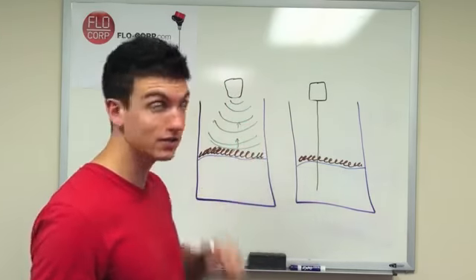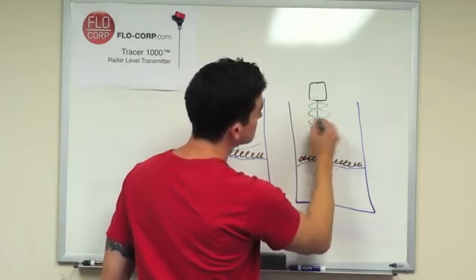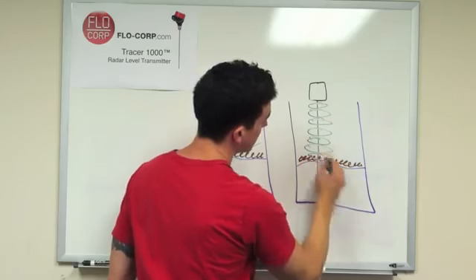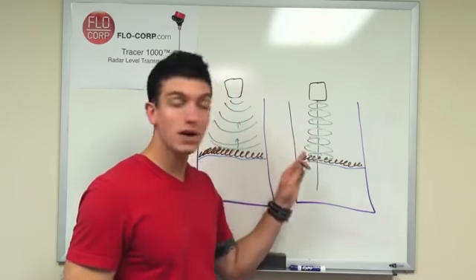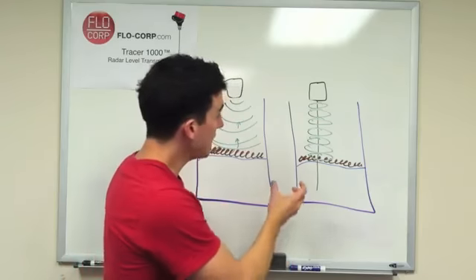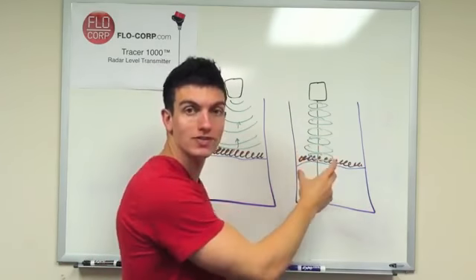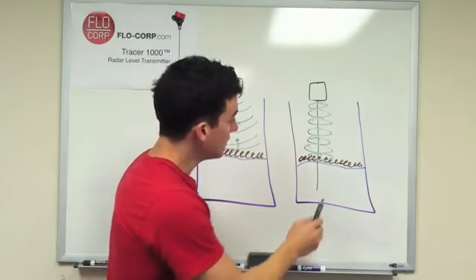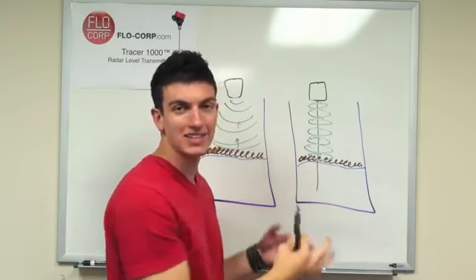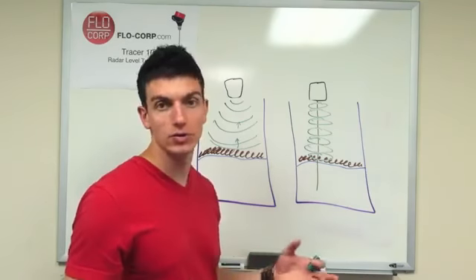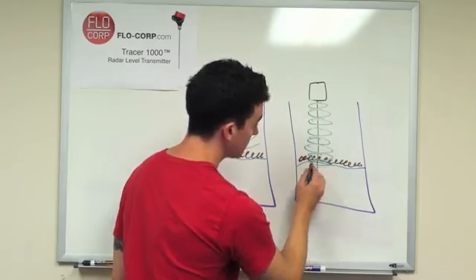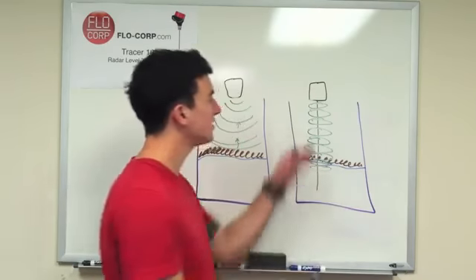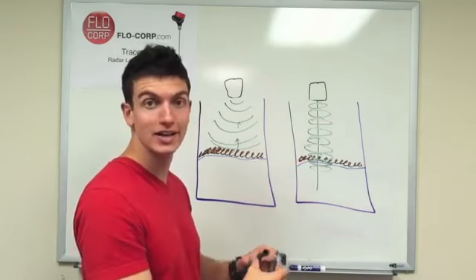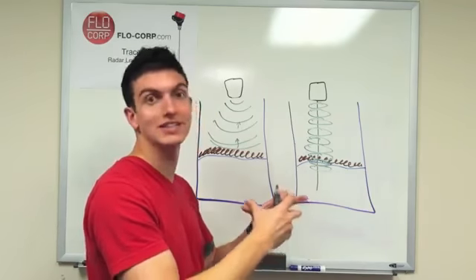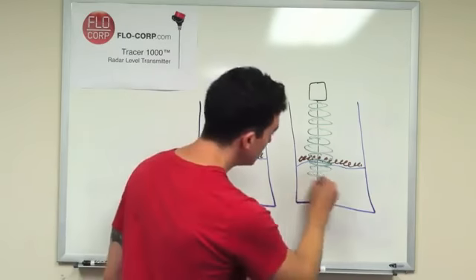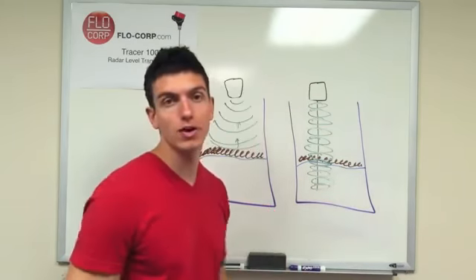All right, so radar, how does that compare? Because radar uses microwaves, it can't really pick up foam the same way it does a liquid. So even though it takes a measurement here, it doesn't recognize it as the surface of the liquid you're trying to measure. It continues down. It's going to start taking measurements here. I mean, it takes measurements all the way down, but what I mean is it's going to start reading that it's in the liquid, or it's taking a real measurement. And it'll continue on down to the bottom of the probe.